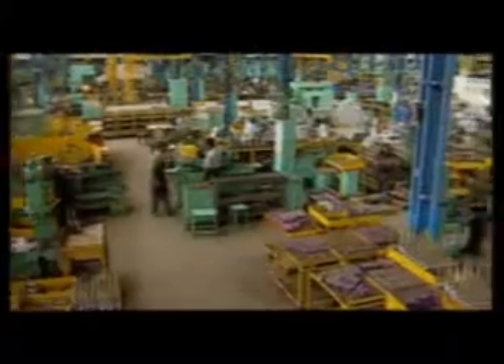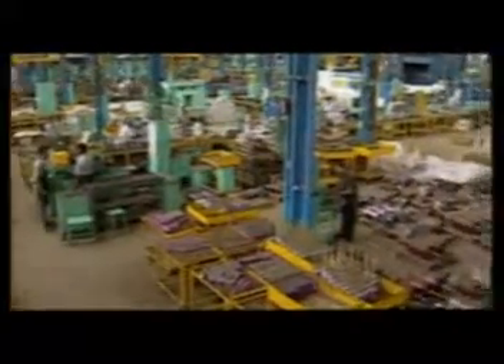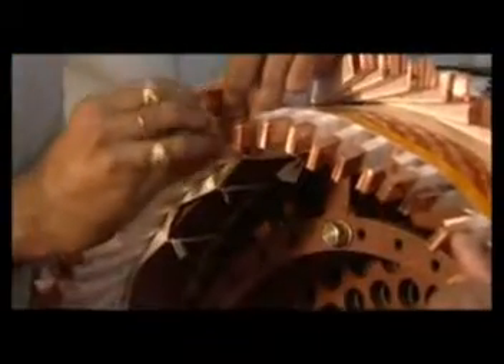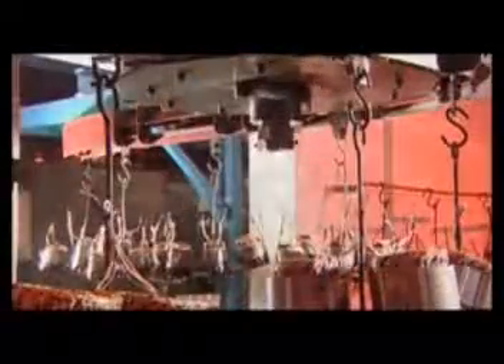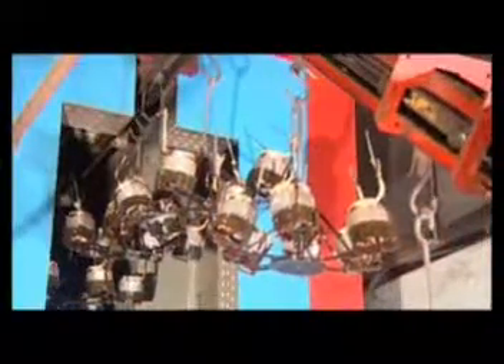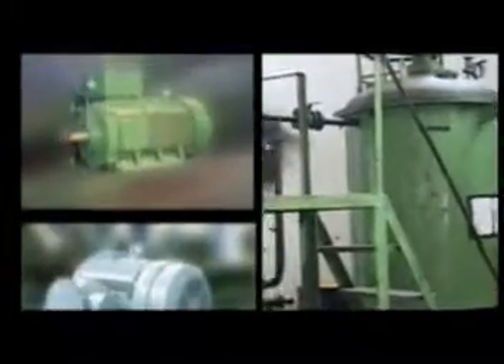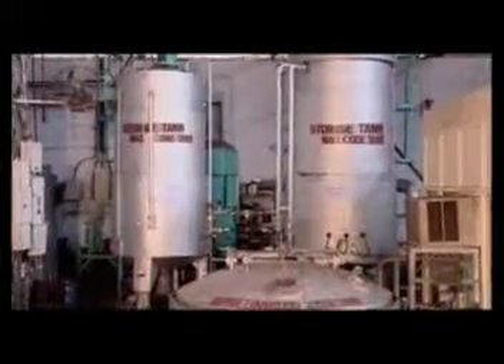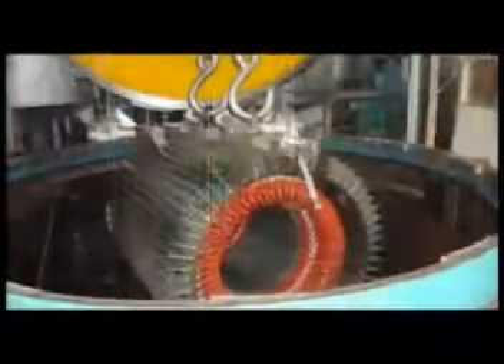Low-voltage motors and industrial fan motors manufactured at Paharpu Works have coil winding using round enameled wires. Rotors for large frames have bar-wave winding for slip ring motors. Conveyor-based dip impregnation systems for up to frame 200 ensure high productivity for lower frame sizes of motors. Motors of higher frame sizes are vacuum pressure impregnated, as are most medium-voltage motors.